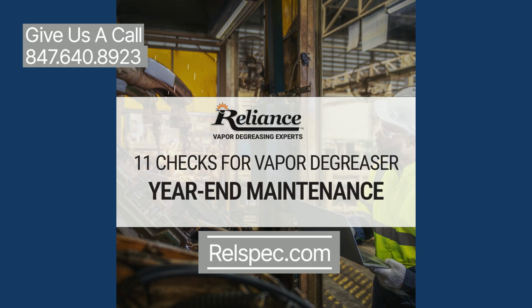A. Clean all debris from the heating elements. B. Check the amp draw or conduct an ohm test on each element to ensure it is functioning properly. C. Check for damage to the heating element's surface, such as corrosion, cracks, or signs of bulging. These conditions often are precursors of element failure. D. Check all door gaskets and all heating element Teflon washers for damage. Replace any gasket or washer that shows signs of damage.